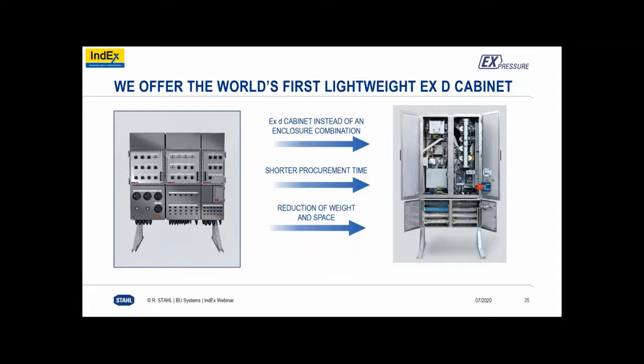Yeah, if we are talking about years, the cost of maintenance and repairs, compared with installation of the enclosure or the solution against a conventional Ex d solution, is cheaper for the owner. So you save time, you are saving personnel, you are also saving cost by using one single cabinet instead of a combination of many. So to give input from a design, installation, operation, and maintenance perspective, yes, the material costs are higher, but the EX design costs are lower. The time is shorter, so the cost is lower.